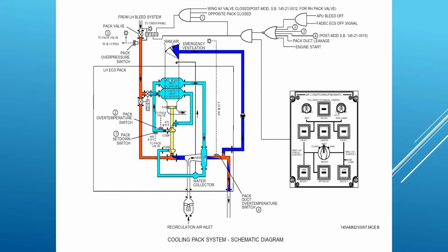So we've now got nice dry air that's been cooled from the secondary heat exchanger, although there's still a lot of thermal energy there. You certainly wouldn't want to touch it with your hands, it would be really hot. And it then comes to a turbine. Now the turbine, we're going to make the air do work. That means it's going to give up its heat energy. We're also going to expand it and reduce the pressure, so the temperature will also drop. So the temperature will drop through expansion, pressure reduction, and by making it do work. The work that it does is driving the compressor and the fan. So when it leaves the turbine, it's cold. At altitude, that can be really cold, maybe 3 degrees C, something like that.